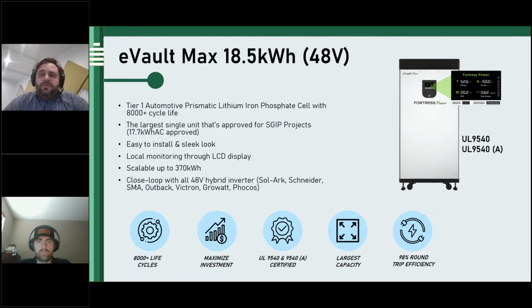That is an improvement from the eVault Classic product line, which could only support up to 2 batteries in parallel with closed loop communication, or up to, I believe, 12 batteries in parallel in voltage-based control without that communication. Now with the eVault Max, we upgraded the BMS system to support a more robust battery to inverter communication platform, and that enables these batteries to actually go into the commercial marketplace with commercial battery sizes.